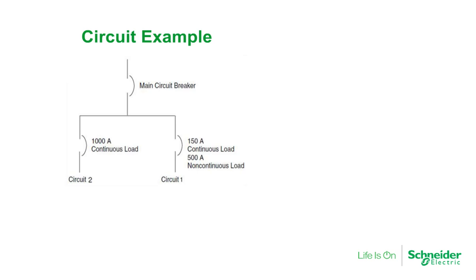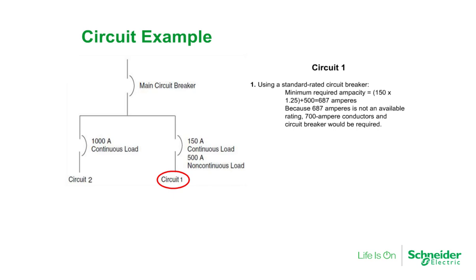Now let's take a look at some circuit design examples. In this example, there are two branch circuits being fed from the main circuit breaker. Looking at circuit number 1: when using a standard rated circuit breaker, the minimum required ampacity would be 150A times 1.25 — derived from the NEC requirement of 125% loading — plus 500A for the non-continuous load, which yields 687A. Because 687A is not a standard rating, a 700A conductor and circuit breaker would be required.